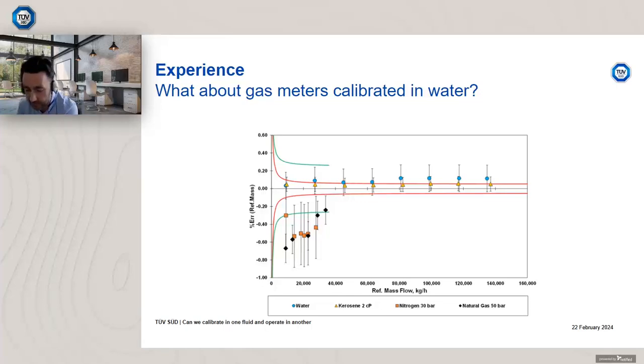So say for example, in gas you're operating from 20 to 80% of the gas flow range. If you were calibrating in liquid, you would then try and match 20% to 80% of the liquid flow range, but also match at least 2 mass flow rates as well, just to give you an idea of what the range looks like. You'll find that Coriolis meters are inherently linear devices. They should be extremely linear. So your liquid calibration should be linear, certainly at the higher range. The challenge is certainly down at the lower range, where these zero effects can certainly dominate.